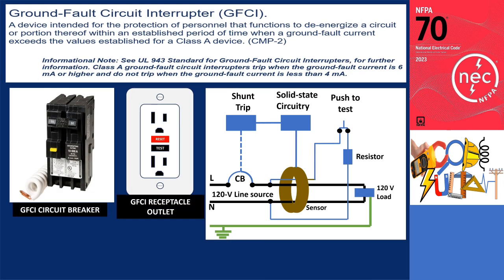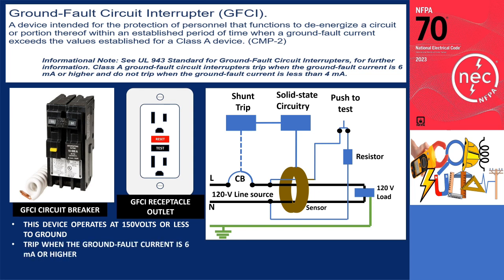A ground fault circuit interrupter (GFCI) is a device intended for the protection of personnel that functions to de-energize a circuit or portion thereof within an established period when a ground fault current exceeds the values established for a Class A device. A photo shows an example of a GFCI circuit breaker and outlets. These Class A devices operate at 150 volts or less to ground. This ground fault circuit interrupter trips when the ground fault current is 6 milliamperes or higher, and does not trip when the ground fault current is less than 4 milliamperes.